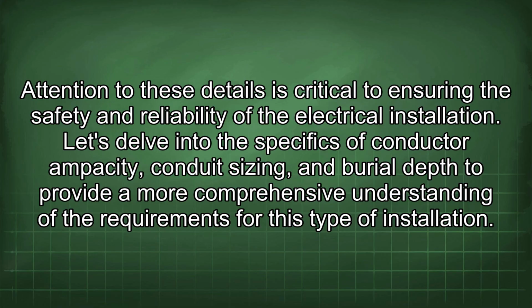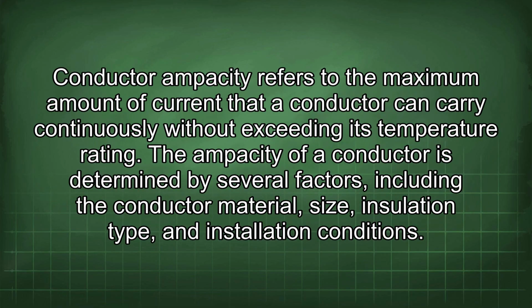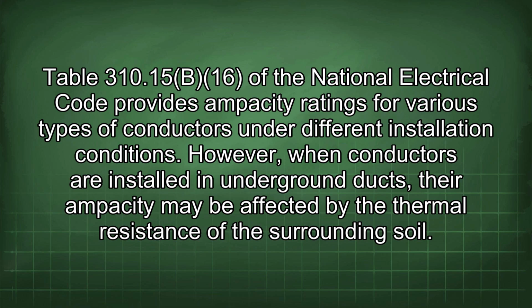Let's delve into the specifics of conductor ampacity, conduit sizing, and burial depth to provide a more comprehensive understanding of the requirements for this type of installation. Conductor ampacity refers to the maximum amount of current that a conductor can carry continuously without exceeding its temperature rating. The ampacity of a conductor is determined by several factors, including the conductor material, size, insulation type, and installation conditions. Table 310.15 B16 of the National Electrical Code provides ampacity ratings for various types of conductors under different installation conditions.